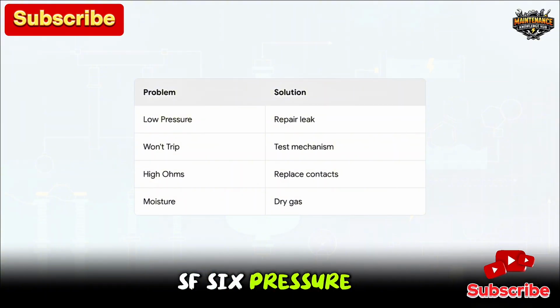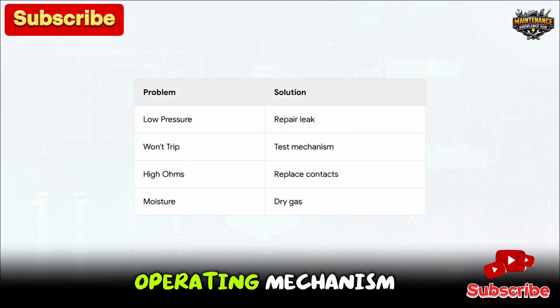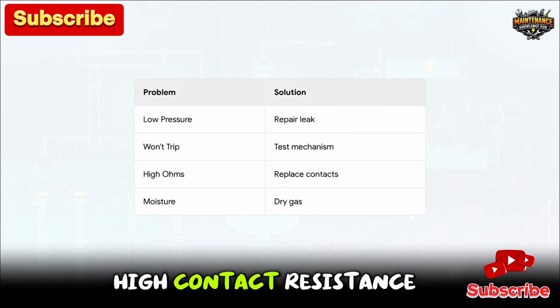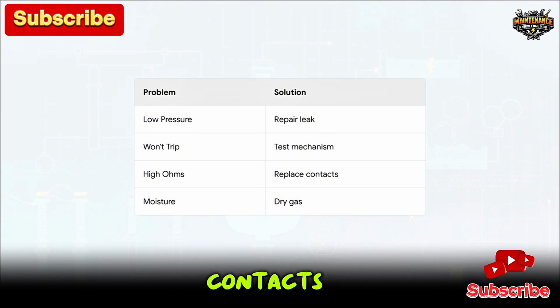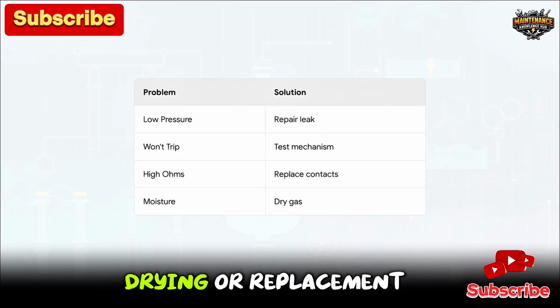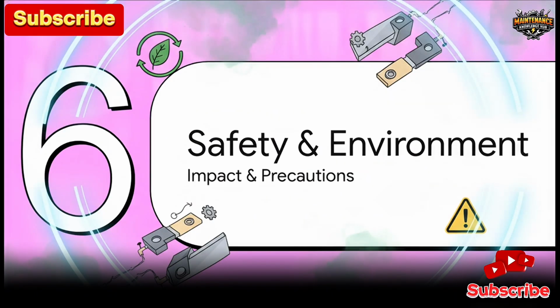But, things don't always go perfectly, which is exactly why technicians rely on strict troubleshooting matrices. If there's low SF₆ pressure, the cause is almost certainly a gas leak, which means an immediate repair and refill. If the breaker fails to trip, which by the way is an absolute nightmare scenario during a fault, the technician knows to immediately go test the trip coils, relays, and the operating mechanism. High contact resistance, that points directly to worn contacts that need immediate replacement. And if moisture somehow gets in, it usually means a seal has failed somewhere, requiring a complete drying or replacement of the gas.